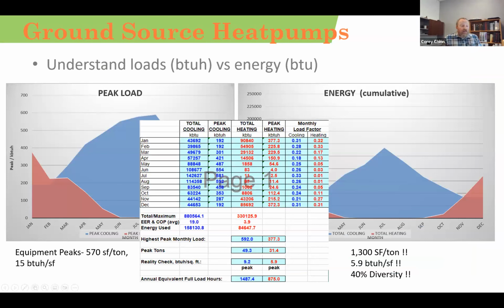All right. So as we all know, it's important when we talk about geothermal versus traditional systems, we're not talking apples to apples. A traditional system, we'd be sized out about 570 square foot per ton. About 500 square foot a ton and probably 30 BTU per square foot. In this project, our ground source heat pumps, because of the benefits to the envelope and the lighting, our sum of peaks is 570 square foot per ton and 15 BTUH per square foot, which is pretty incredible when you look at it. But then our ground loop is sized at 1,300 square foot per ton and 5.9 BTUH per square foot. So if you understand your loads versus your energy, you can do a lot with this stuff.